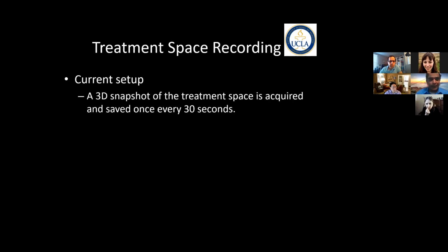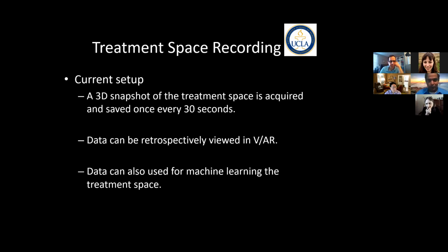Was that a mistake, or did something unexpected happen? It's a 3D snapshot of the 3D treatment space that is acquired and saved once every 30 seconds. So that keeps automatically updating, and data can be retrospectively viewed in VAR systems so that you can verify what happened.